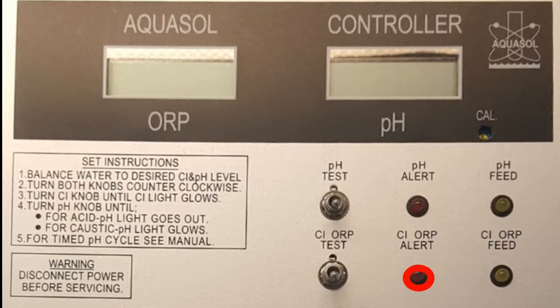Next, we have the CL ORP alert LED. When this is lit, the controller is indicating that the signal coming from the ORP electrode is out of range of the CL ORP control knob. The CL ORP alert overrides the CL ORP feed system. The controller cannot make sanitizer adjustments when in CL ORP alert.